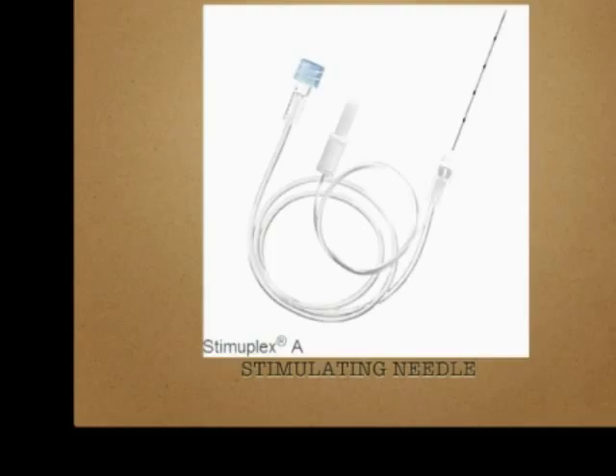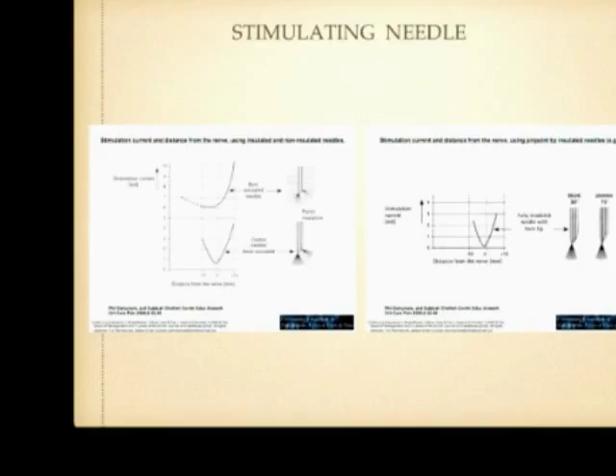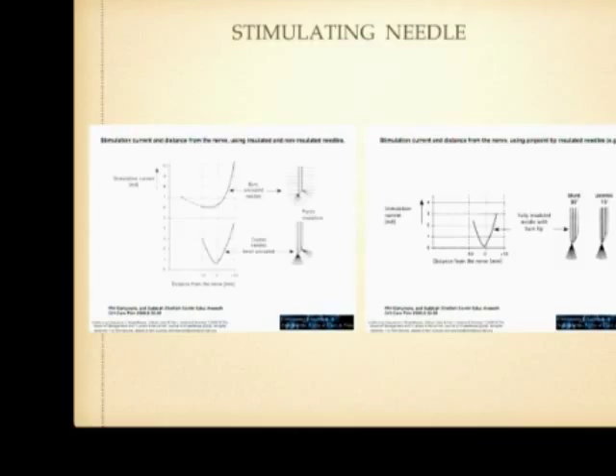Why should the stimulating needle shaft be insulated? If the shaft is not insulated, currents are dissipated from all over the shaft as well as from the tip, requiring a higher amount of energy to stimulate the nerve. But if the needle is insulated throughout the shaft and only the tip discharges electrical pulses, it requires much less current to stimulate the nerve. Nowadays most needles come with a 30-degree bevel, which helps decrease nerve injury if you are close to the nerve.